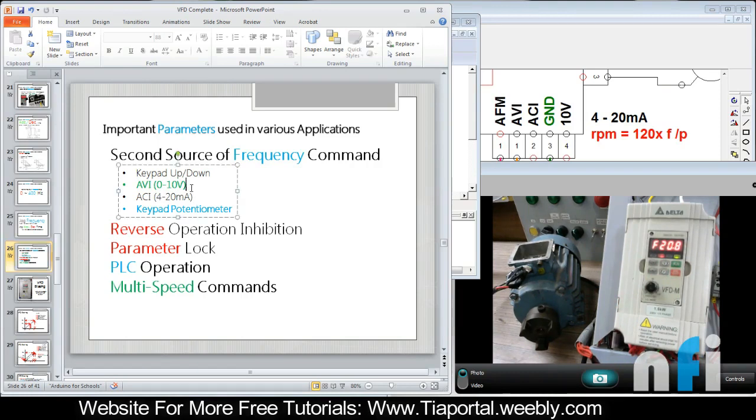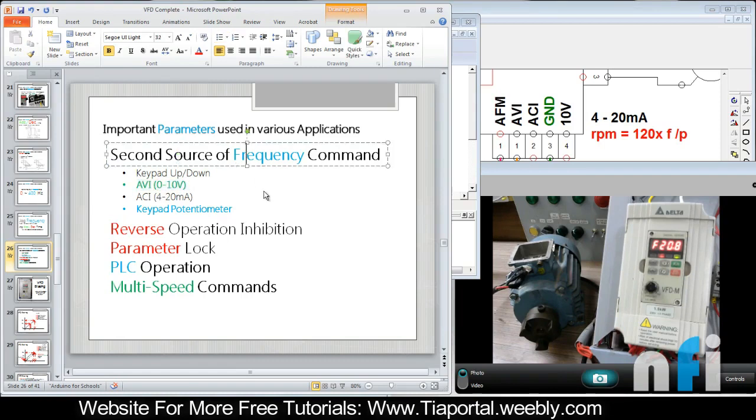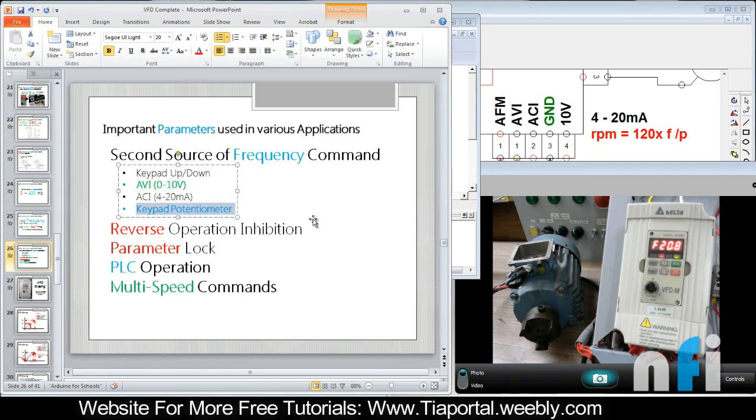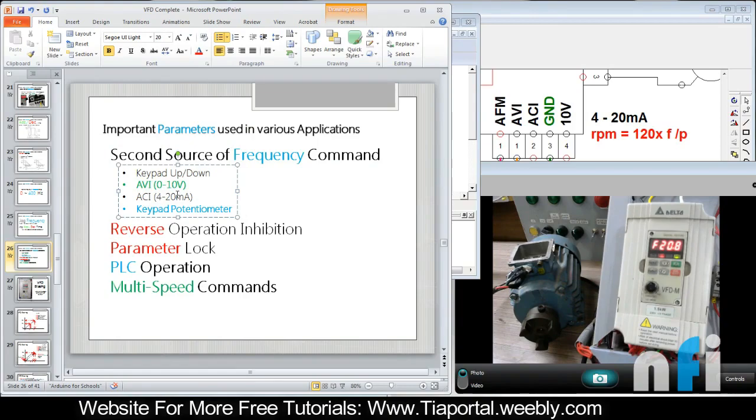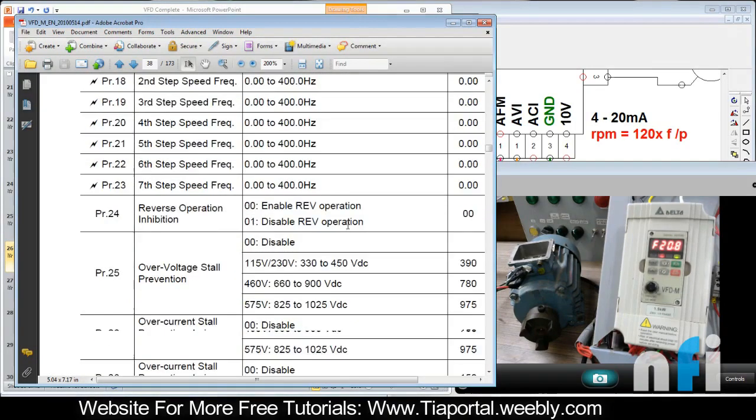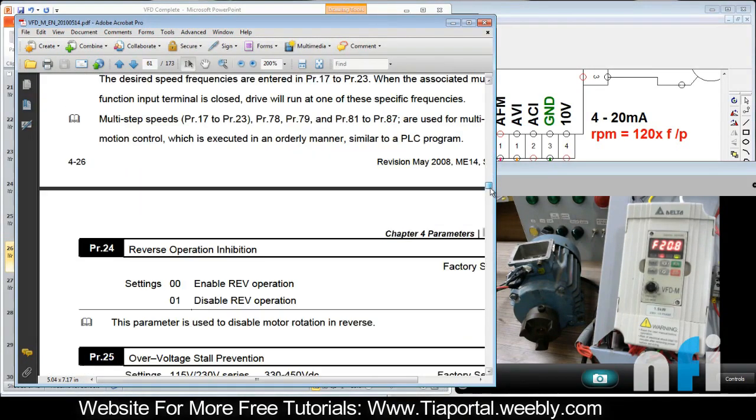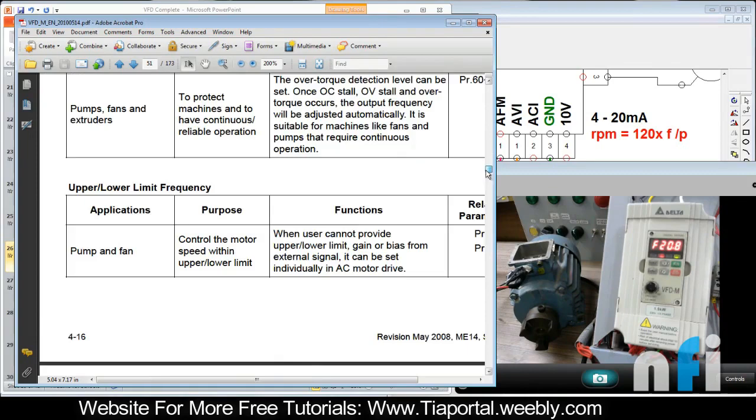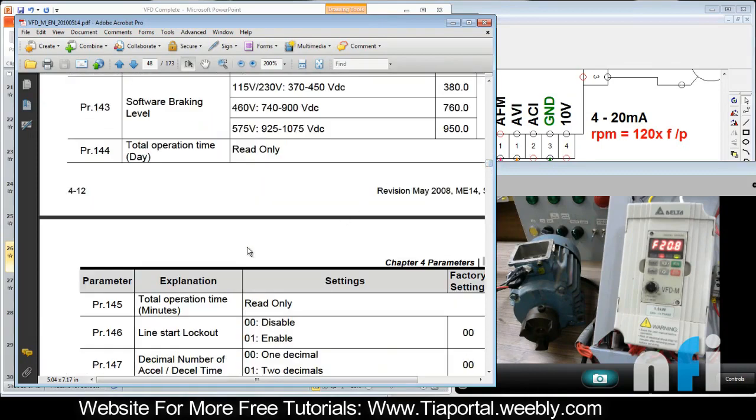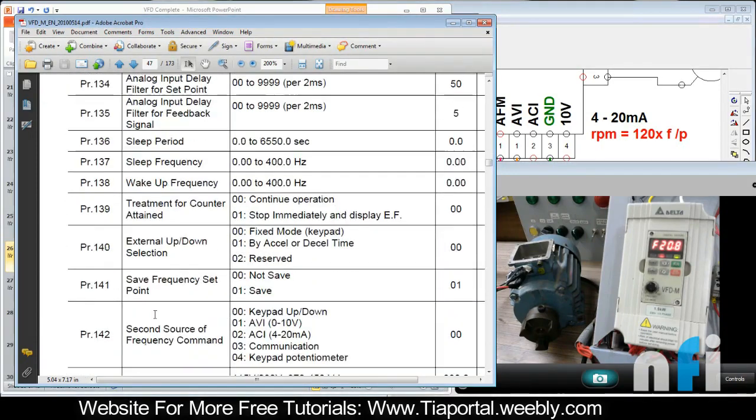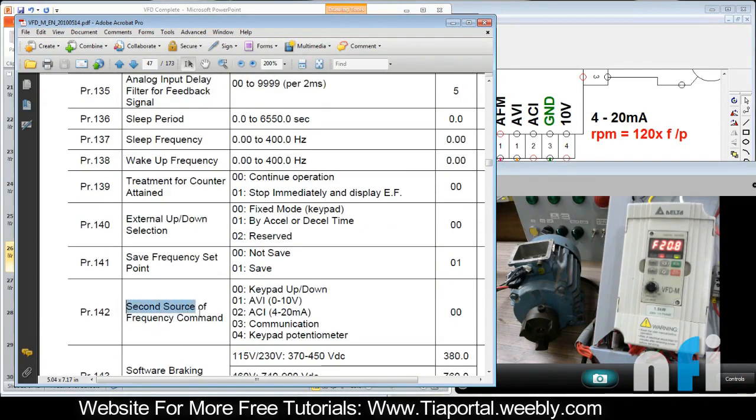First, select your second source. My first source is potentiometer, already selected. Second source I want AVI. You can find in your manual there is parameter 142. This is the second source of frequency. Here I need to set 01.